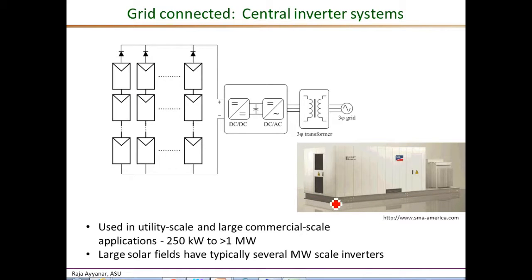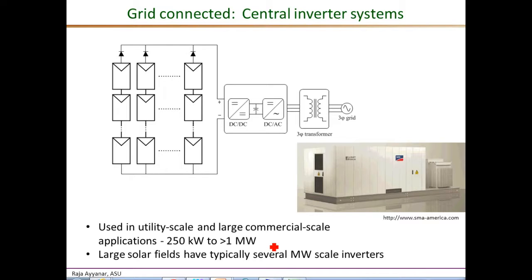Next we come to the more common type of PV inverters: the grid-connected PV inverters. Among these, we look at central inverters first. Central inverters are used in utility scale and large commercial scale applications, with individual inverter power ratings ranging from 250 kilowatts to well above a megawatt. For example, some PV systems on the parking lots of ASU are rated close to a megawatt and are supported by four inverters rated at 250 kilowatts each.